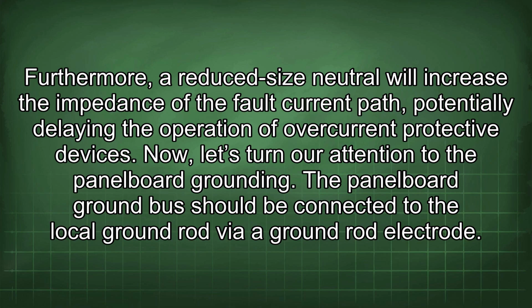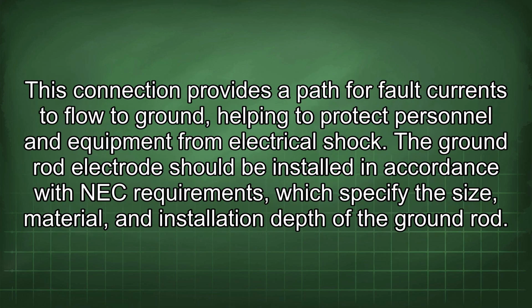Now let's turn our attention to the panel board grounding. The panel board ground bus should be connected to the local ground rod via a ground rod electrode. This connection provides a path for fault currents to flow to ground, helping to protect personnel and equipment from electrical shock. The ground rod electrode should be installed in accordance with NEC requirements, which specify the size, material, and installation depth of the ground rod.